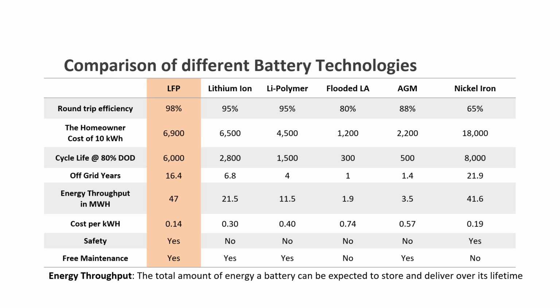Two things I want to showcase in this comparison: energy throughput, which is the total amount of energy a battery can be expected to store and deliver over its lifetime. For LFP, you can expect to store and deliver 47 megawatt hours over the lifetime of the battery. Lithium ion is only around 22, flooded lead acid is only around 2, and the only one that comes close is nickel iron at 41.6.